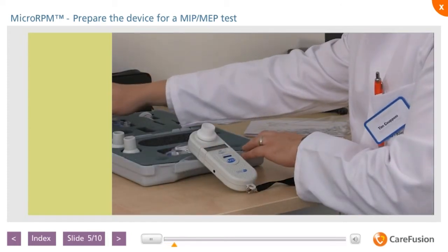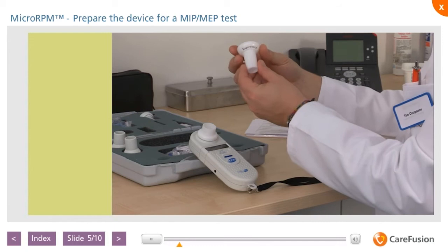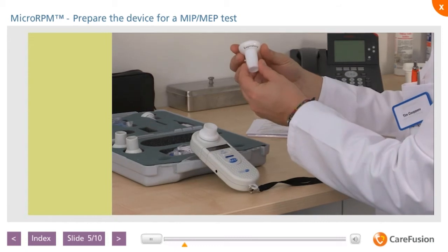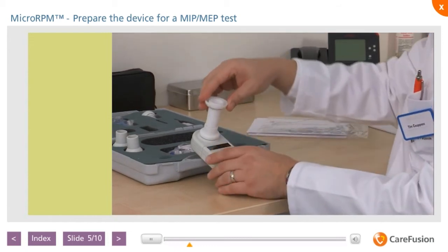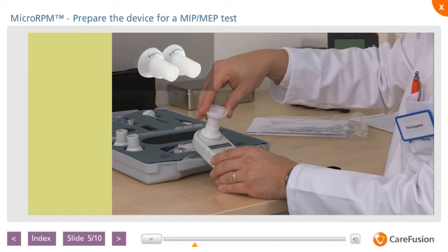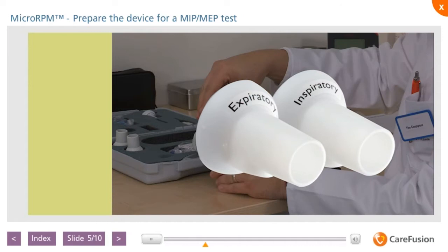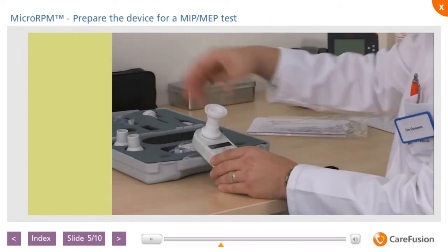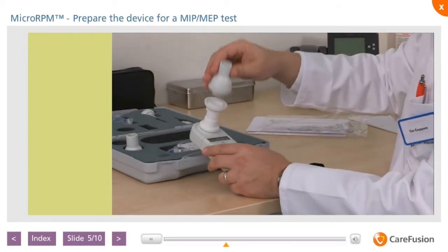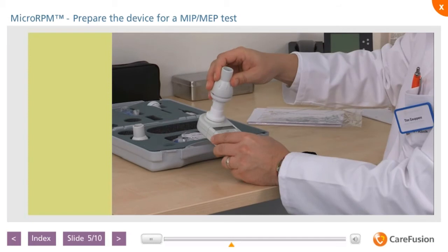The MicroRPM device is made ready to perform an MIP or MEP maneuver by firstly fitting the pressure assembly to the unit. For a PI max maneuver, fit the pressure assembly marked inspiratory. For a PE max maneuver, fit the pressure assembly marked expiratory. Next, fit a bacterial viral filter to the assembly. This will provide protection for the patient and reduce cross-contamination.